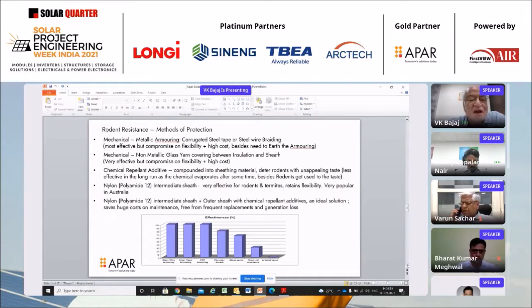Then there's nylon polyamide 12 intermediate sheath. It is very effective for rodents and termites, retains flexibility, and is very popular in Australia. Nylon 12 is a very tough material that resists all rodents and termites. This sheath is provided between the insulation and outer jacket, and it also improves the electrical properties.